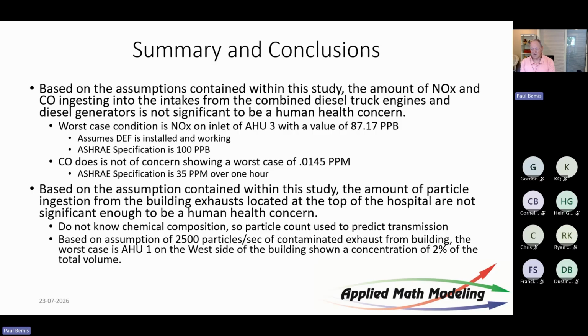It is not common because generally speaking, that's not an issue. It's more a concern about thermal contamination from one air handler to another. But we do model it and we can predict it for data centers or for buildings like this. This one happens to be a hospital. It doesn't have to be a hospital. This concern should be studied and understood, I think, on all commercial buildings. If you have fresh air intakes, we've run into many situations where fresh air intakes are causing issues.